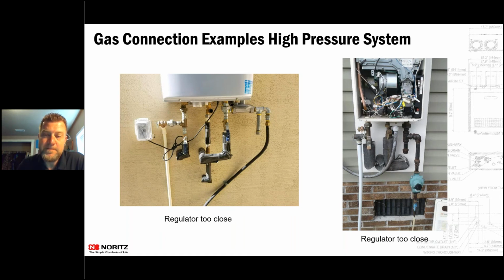This is Vic again. I see a lot of this. I have to go in and resize for people because they put it in and say, well, it says it could be a half-inch gas line, but if you read the fine print, it has to be less than like 12 feet. It has to be the first thing on the gas line, and they don't realize that the furnace came off before, and that's when they start starving it, when the furnace kicks on. So you have to make sure you read the directions, because it says you can use half-inch, but there are a lot of things you have to follow to get it to work.